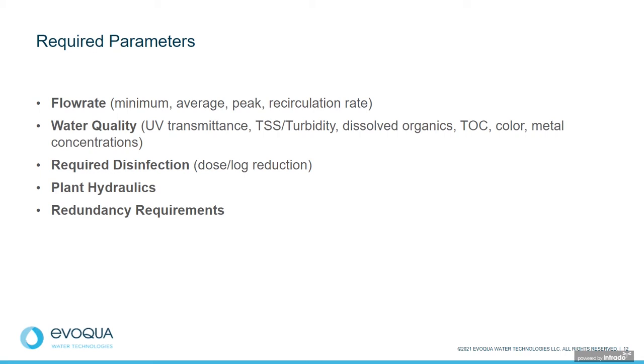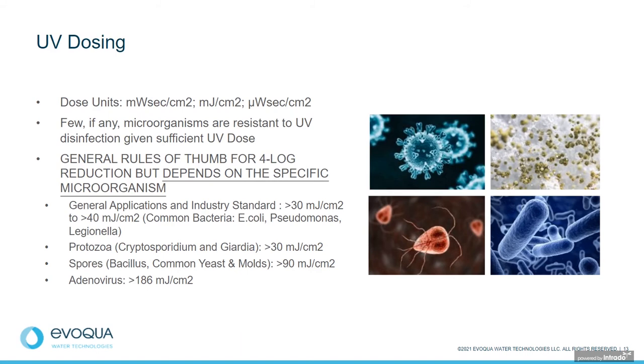The required disinfection. UV is not a sterilization process per se. It is a log reduction method. So if you want to get 99.99% or 4-log reduction of total organisms in your system and you want to remove those, we have to size it accordingly with the proper UV dose. We need to know a little bit about the plant hydraulics, and then if you need redundancy, depending on how critical the operation is. So again, we size UV on what's called UV dose. The dose units are milliwatt seconds per centimeter squared, millijoules per centimeter squared, or microwatt seconds per centimeter squared.